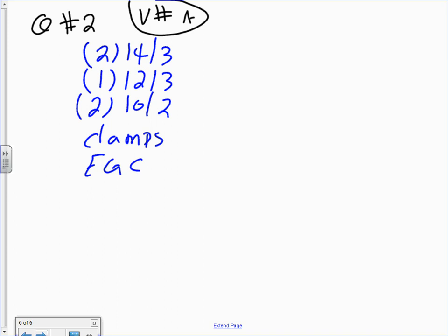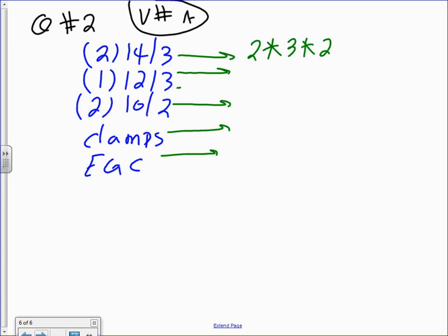And we need to size this box, right? Find the minimum size. That's a piece of cake, guys. We've done that one, right? So I'm going to go directly into it. I put them this way so I can do the math. So the first 2, guys, is for the cables. The second 3 is for the number of conductors. And the third 2, in my case here, is for the equipment grounding for the number 12. So that will give me 12 cubic inch.